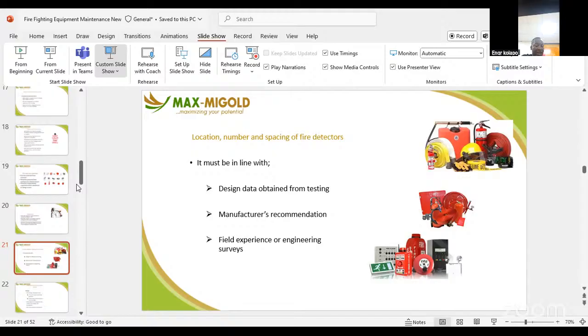So there is the part of the design and there's the part of the use of the facility. You can design something like a hotel and use it for something else. That kind of hazard, the theory behind the hazards, will change. For instance, a warehouse or a factory is just a wide abundance of space. So at that point, you can be looking at installing your smoke detectors at an 81 square meter coverage. Meaning the coverage per smoke detector is about 81 square meters. That is what NFPA 72 has told us.